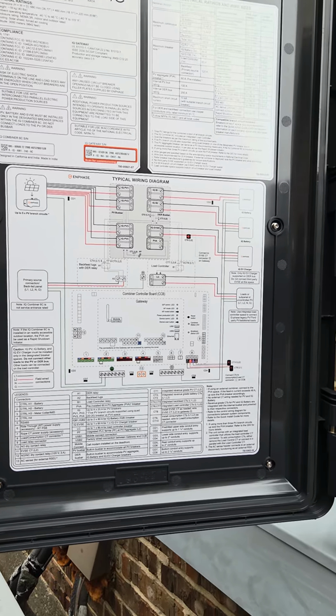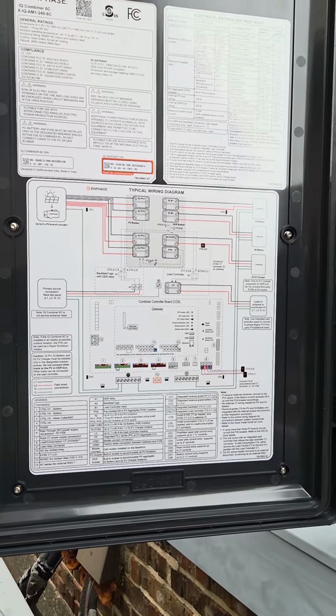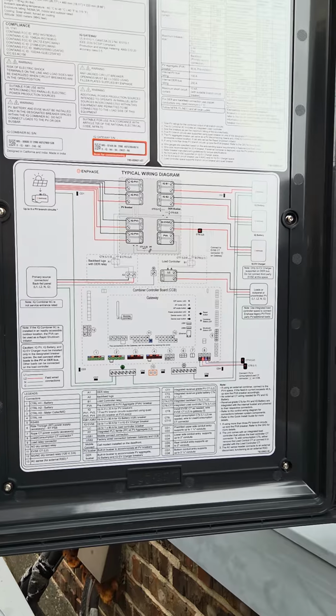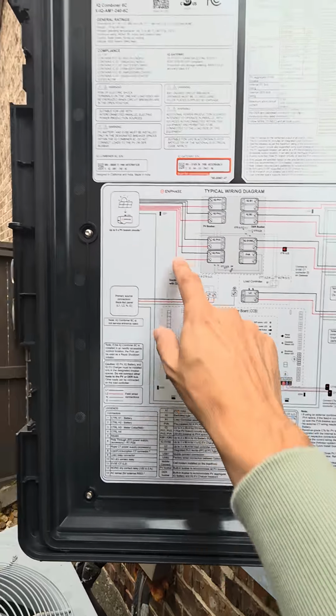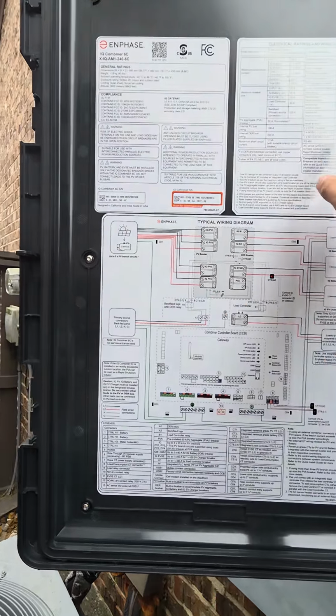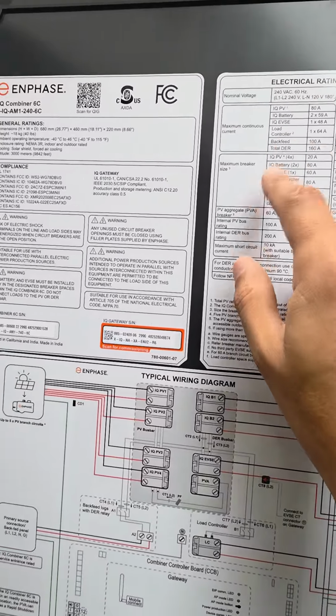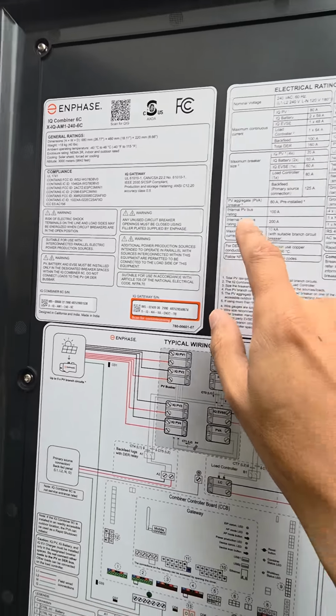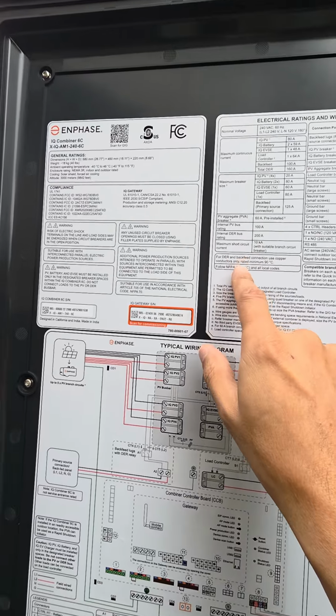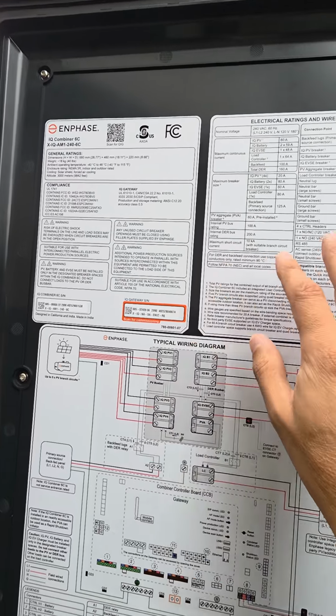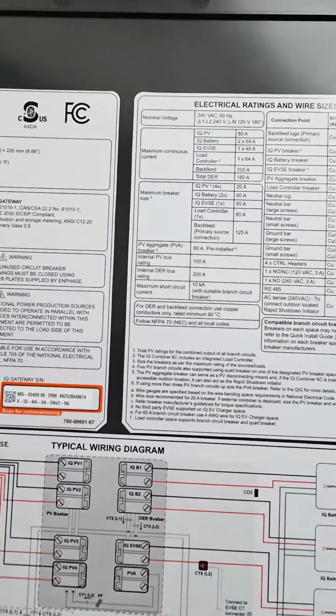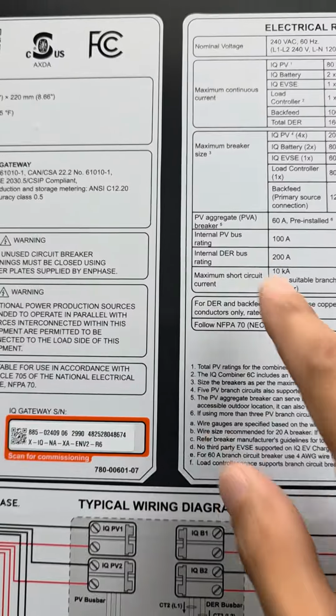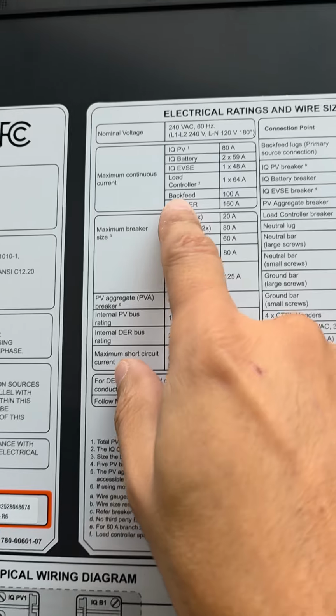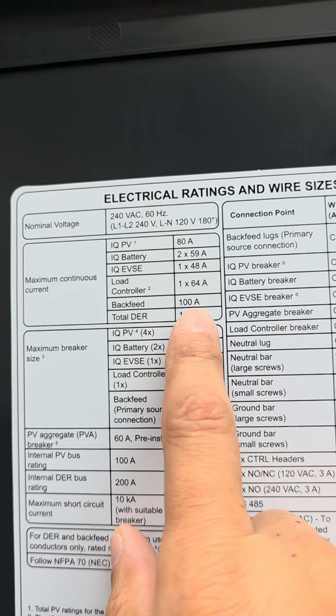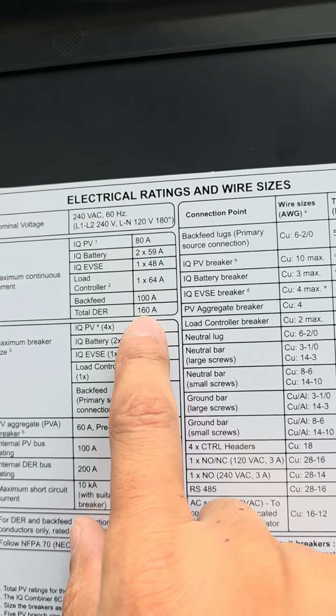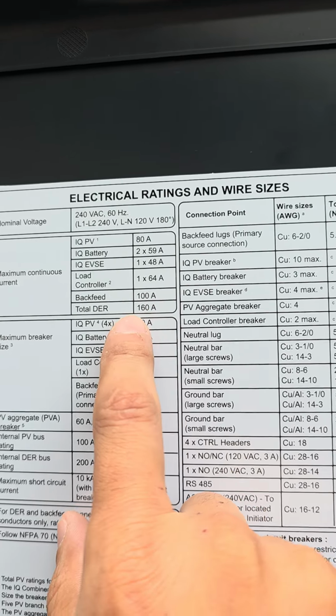I came to a realization pretty quick that I was referencing all kinds of different pages in the manual just to get information that was readily available here. It's got layouts, diagrams, it's got torque settings up here, it's got max amperages, and a big point of contention, and I actually got incorrect information the first time I called Enphase because the system's so new for them as well. It talks about your backfeed, and here's your backfeed, and it says right here backfeed 100 amps, and down here it says total distributed energy is 160 amps.